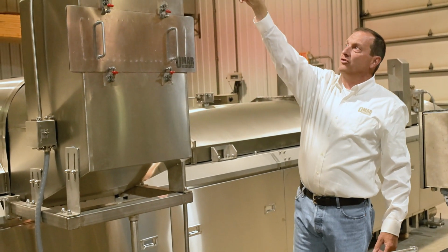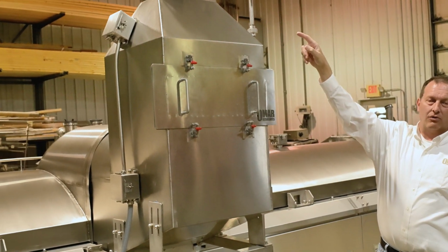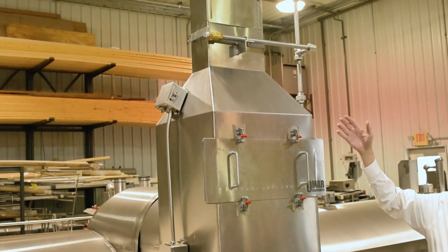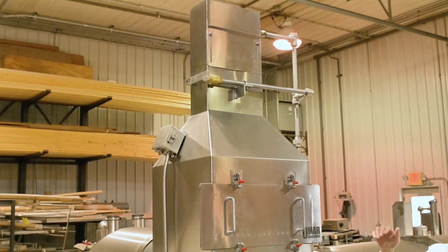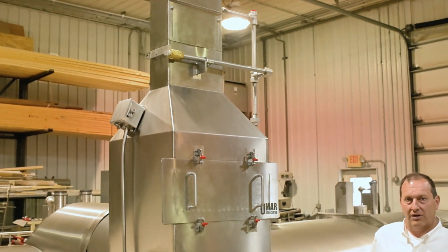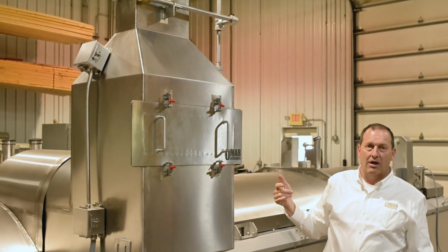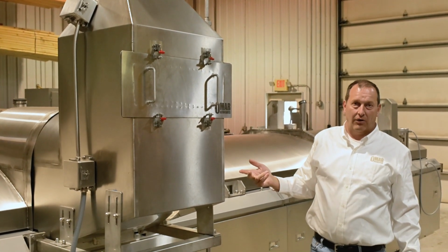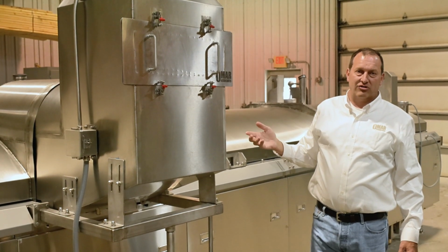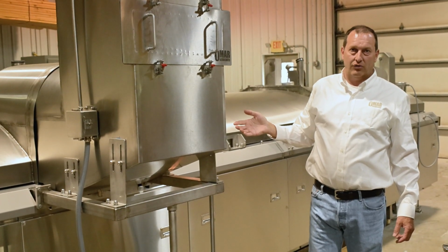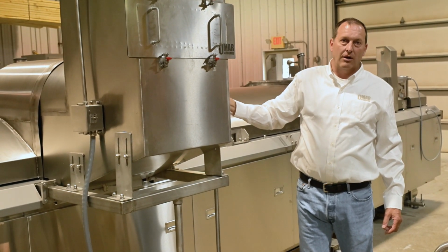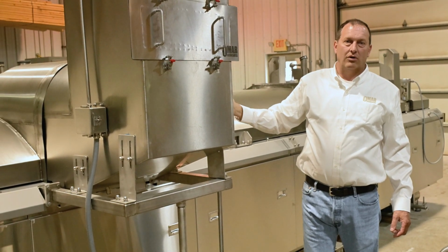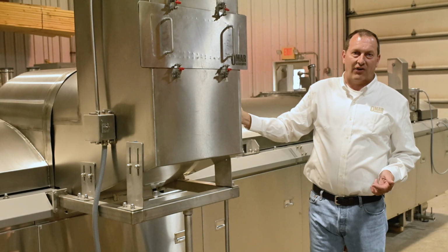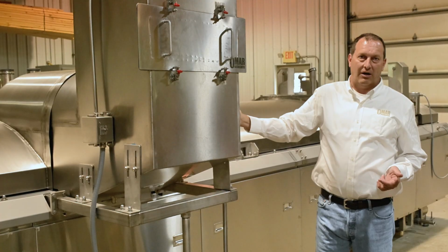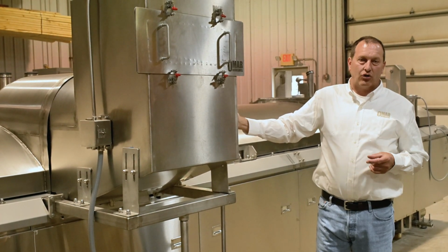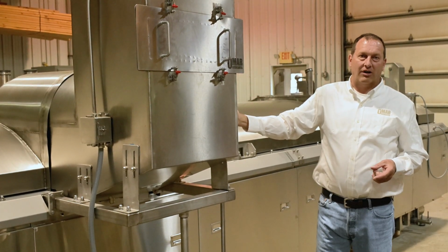There is a pressure trip at the top with a damper door. So when the fire suppression is released, that damper closes, and simultaneously it shuts off all the controls in the fryer. So the exhaust system is shut down, the heat source is shut down, the conveyors are shut down. In addition to that, the fire suppression supply, which typically is CO2, in this case it's high pressure CO2, is released. That CO2 smothers the fryer, snuffs out the fire by removing the oxygen from the volume inside the fryer, and then it cools the cooking oil to the point where it doesn't reignite.